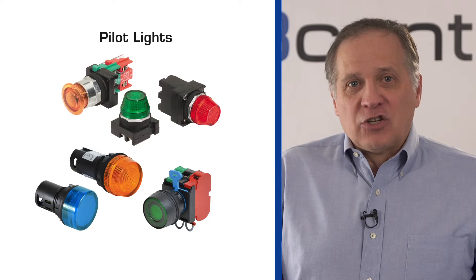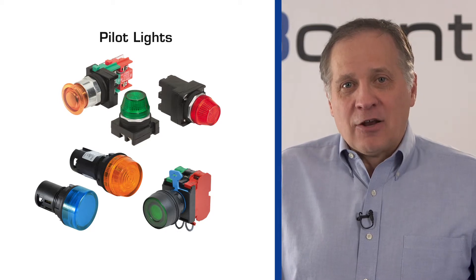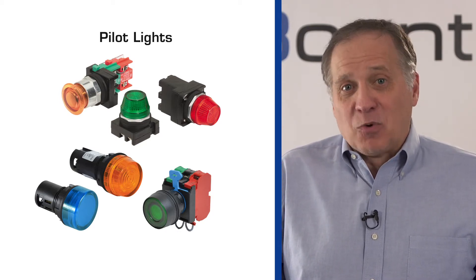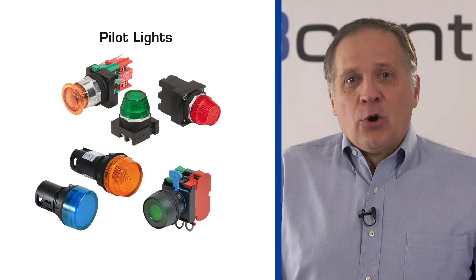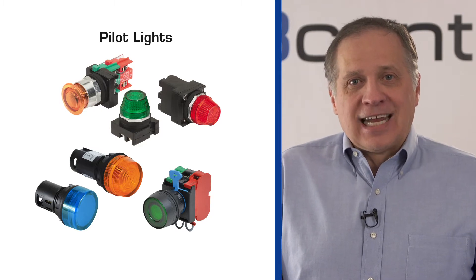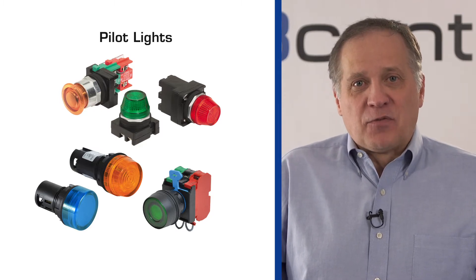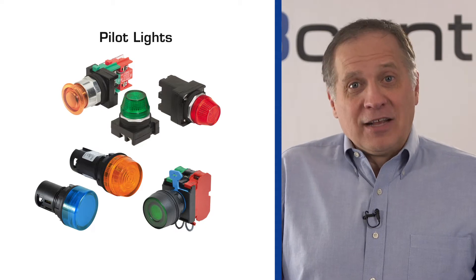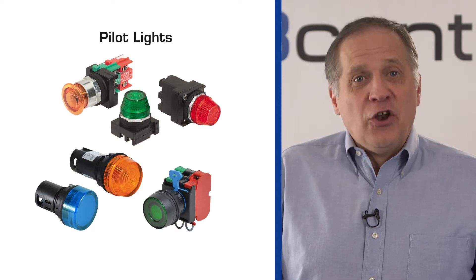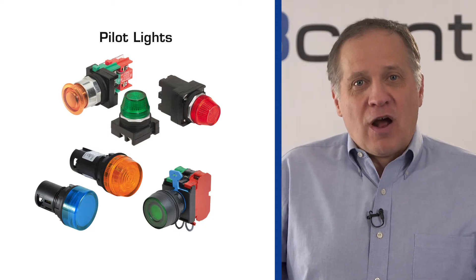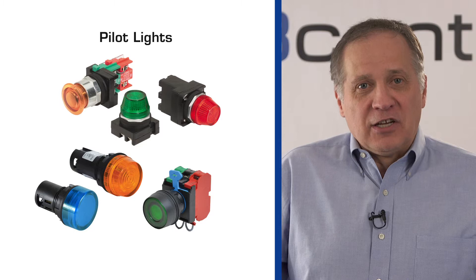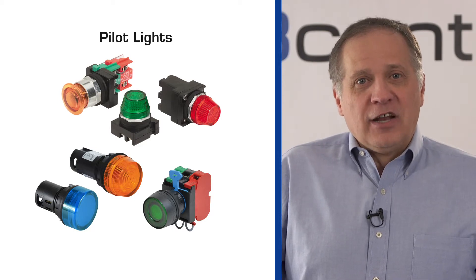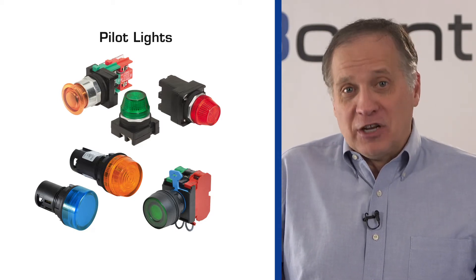An indicator light is equipped with an incandescent lamp or LED and is mainly used in automated instruments, condition panels, and dashboards. Relampable pilot lights feature a lens that can be replaced from the front of the device when they stop functioning. Non-relampable pilot lights are offered as one-piece devices with a fixed lens, meaning the whole indicator needs to be replaced if the light stops functioning.